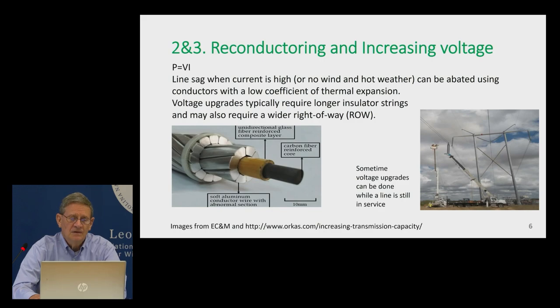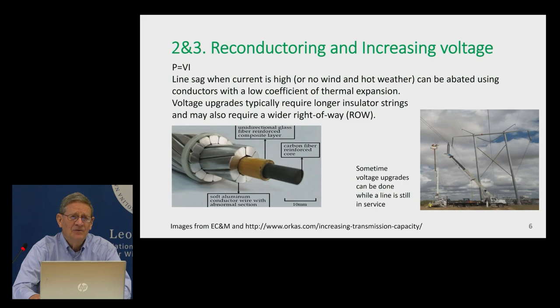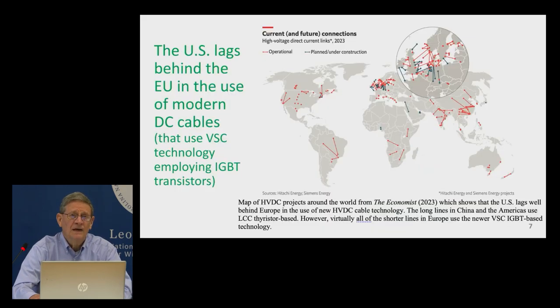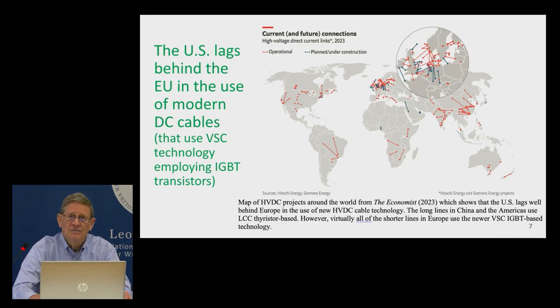The amount of power you can move through a line is, to first order, the product of the current and the voltage — increase either or both, and that helps. The reason for low-sag conductors is that when a lot of current flows through a line, the line gets hot, the metal expands, and the line sags. But there are new technologies that allow you to overcome that.